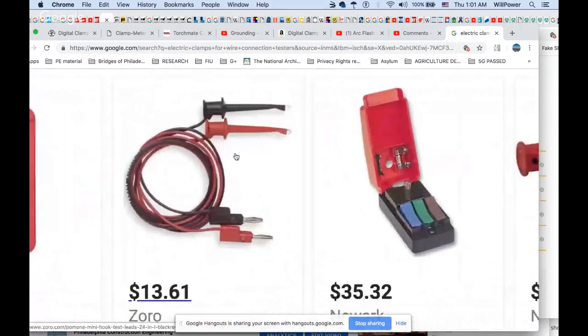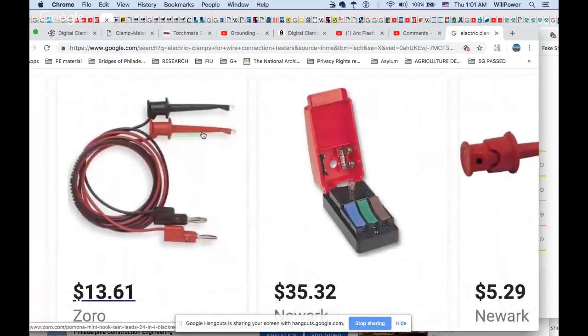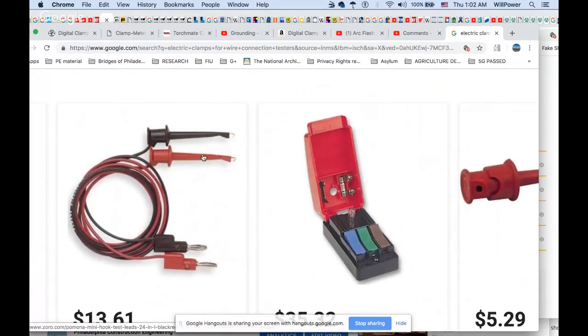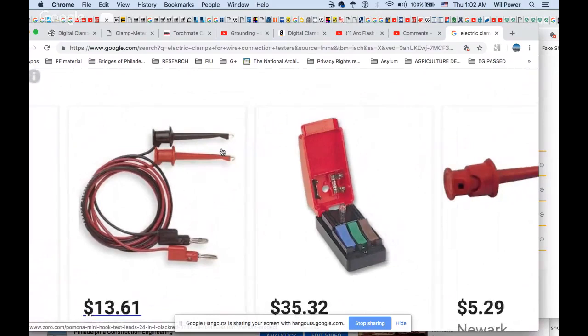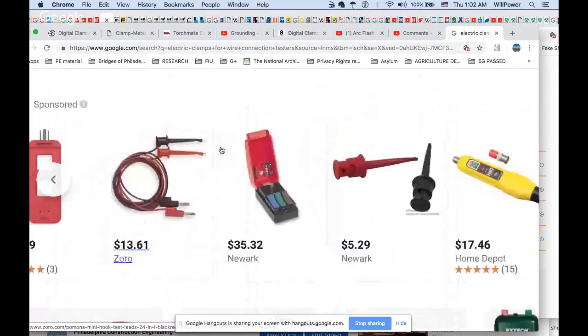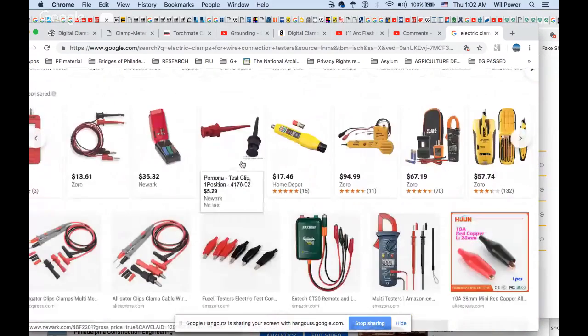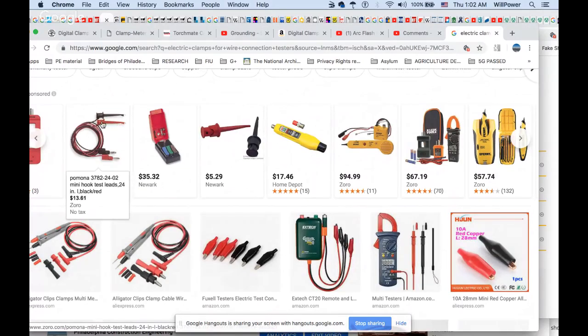Here's your clamps. You always hook up your ground or neutral first, since neutral could accidentally be getting a current. I clamp this one, and then when I go to touch the other one, if it does short out, hopefully it always has this connection there, so instead of routing through me, it routes through the clamp and shorts out and arcs on the box. That's never happened yet, but that's ideally how I'd like to see it fail, not me holding it and getting a blast in my face.